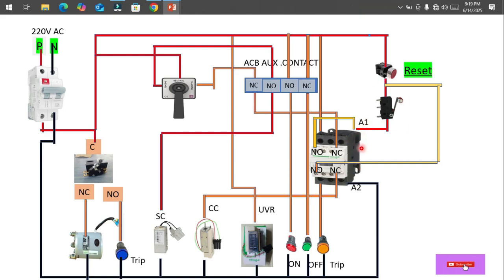When any fault occurs, the NO contact of the fault micro switch becomes NC, so the contactor gets activated. At the same time, the trip indicator glows. The contactor holds itself through its own auxiliary contact, implementing a holding circuit to latch the trip condition.